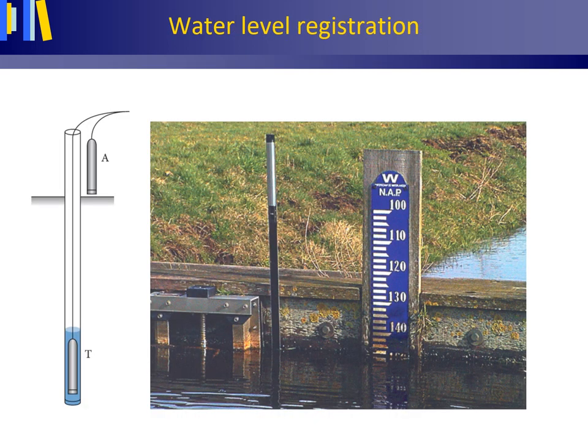To measure the water height, increasing use is made of pressure sensors. A pressure sensor is lowered in a pipe that has openings to enable water to flow in. The sensor is lowered to the bottom of the stream to measure the total pressure, which equals the water pressure plus air pressure. Another pressure sensor is positioned above the water to measure the air pressure. The difference between the total pressure and air pressure gives the water pressure, which is linearly related to the water height or stage. A similar setup was described earlier for determining the hydraulic head of groundwater in a piezometer. The photo shows part of such a setup with a pressure sensor to measure the air pressure on top, plus a staff gauge — a graduated scale — that can be manually read off and used as a check.